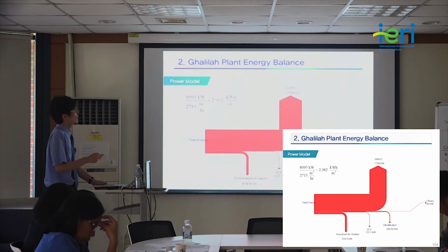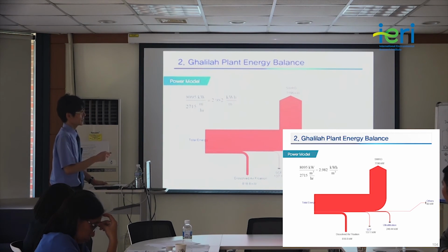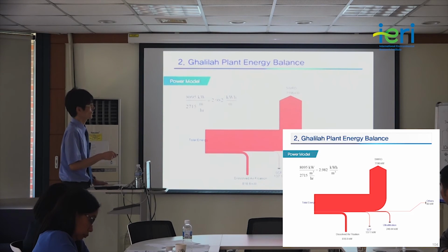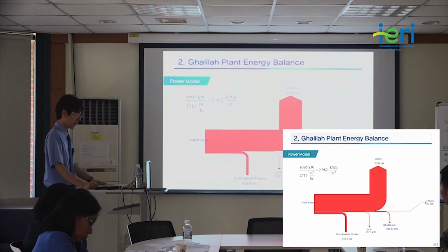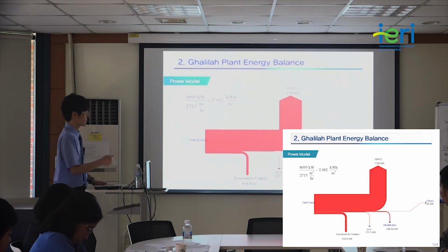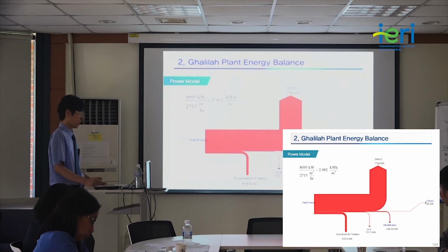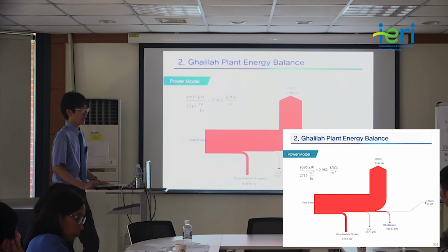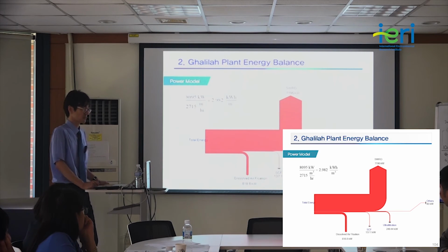So it means that they did not successfully reduce the energy consumption for the reverse osmosis, but they were able to reduce the energy consumption by other parts. So total energy consumption is very low according to this kind of calculation and according to the data from this plant. So this example also shows how we can analyze the energy flows and energy consumptions in a real plant.